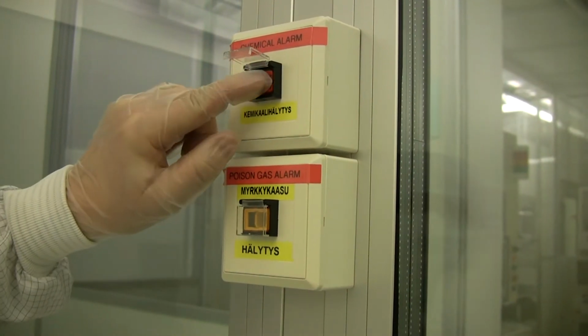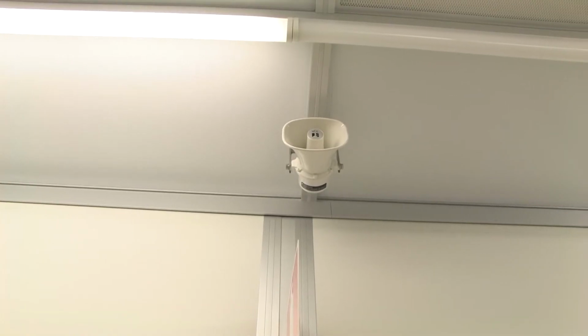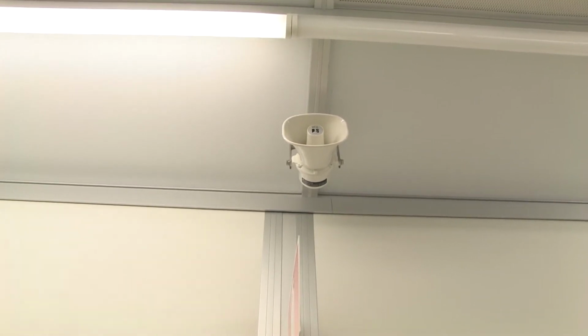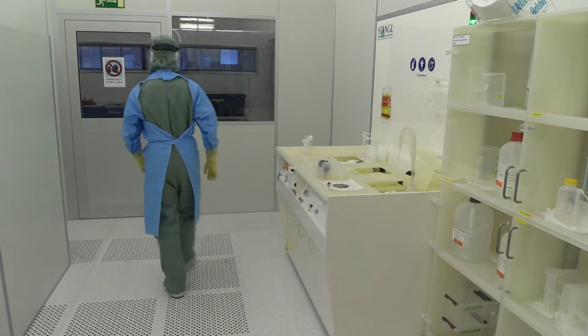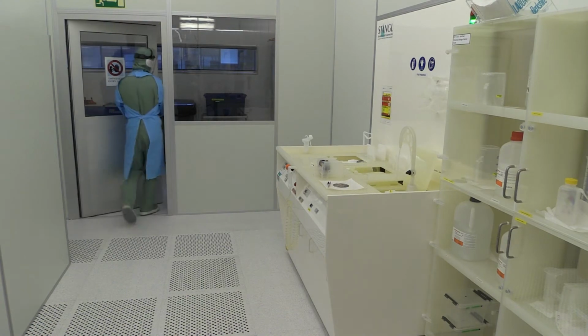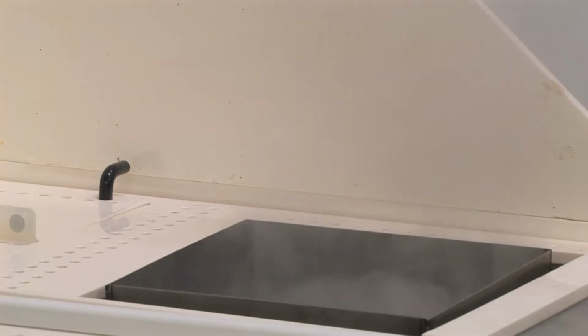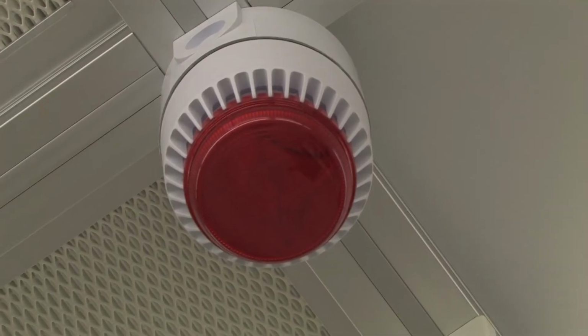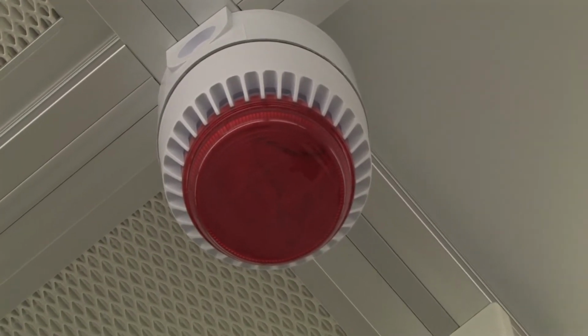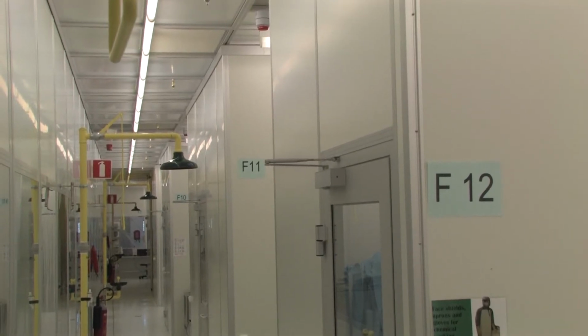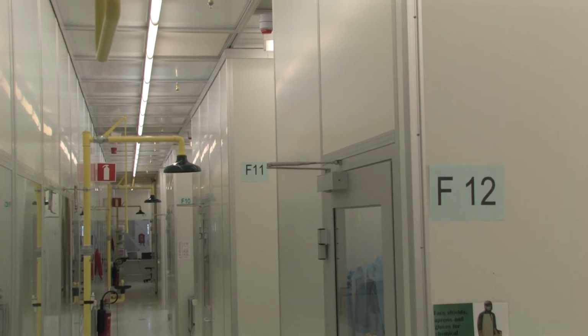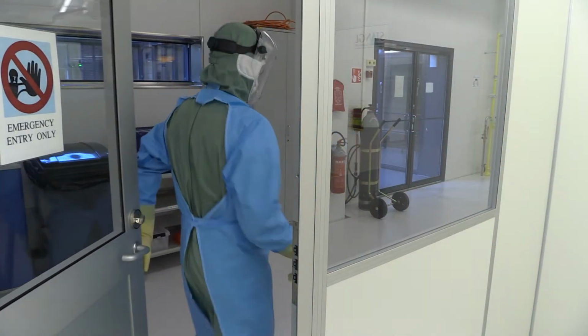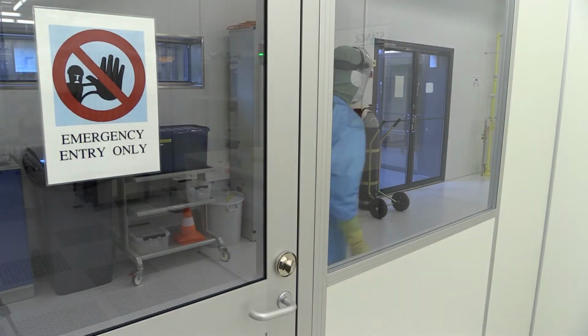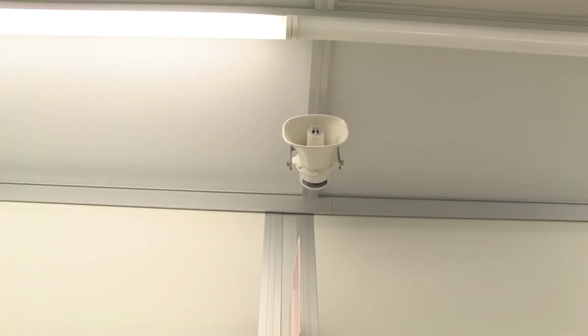If strong chemical fumes are released into the cleanroom for any reason, activate the chemical alarm manually. Chemical danger. Please leave the clean room and technical area. This is the quickest way to evacuate the cleanroom and prevent people from being exposed to the chemical fumes. Chemical alarm is only heard in the cleanroom and the technical areas. When you hear this alarm, leave the cleanroom via emergency exits. If you activated the chemical alarm, inform the rescue team.